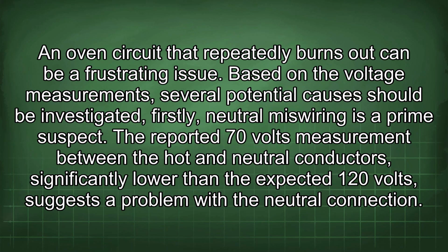An oven circuit that repeatedly burns out can be a frustrating issue. Based on the voltage measurements, several potential causes should be investigated. Firstly, neutral miswiring is a prime suspect. The reported 70 volts measurement between the hot and neutral conductors, significantly lower than the expected 120 volts, suggests a problem with the neutral connection.